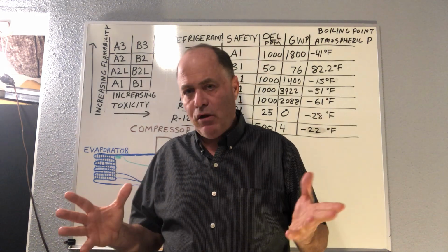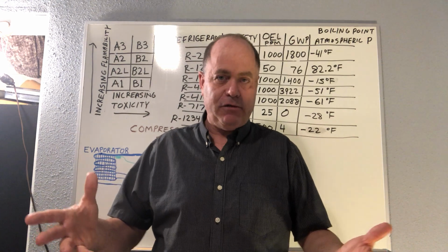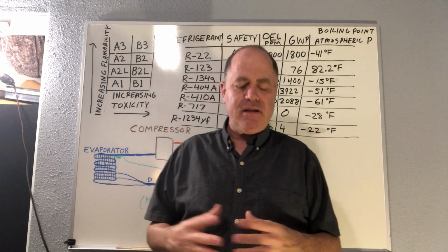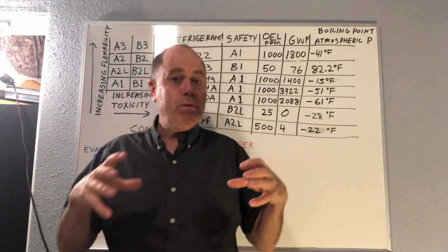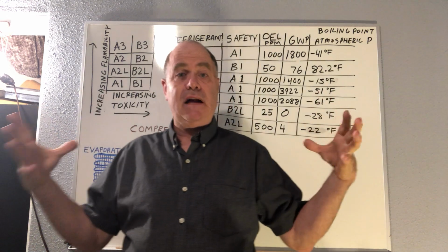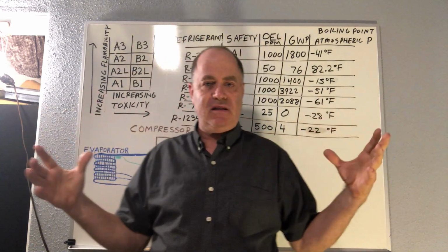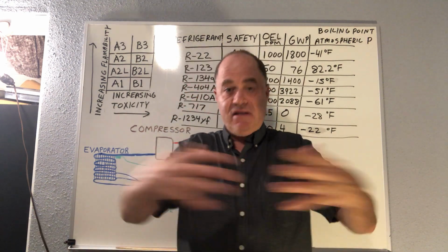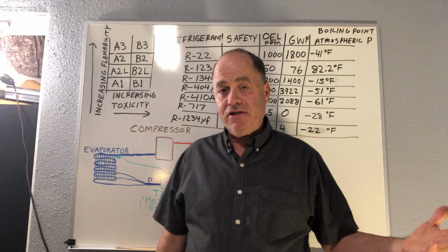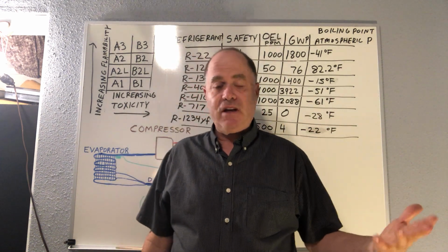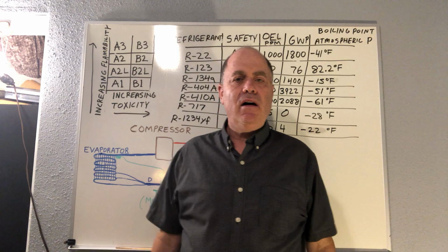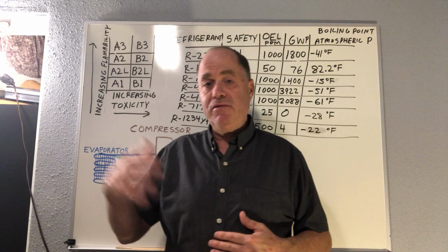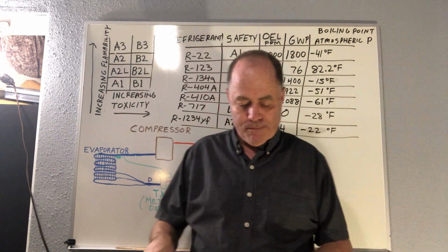So even though they're kind of high probability systems that you could get some refrigerant in there, that's okay according to the code. Then low probability systems are where we actually put our big equipment that holds a lot of refrigerant, because those aren't in occupiable spaces. If something holds a tremendous amount of refrigerant, you don't want it to be where people are, because a giant leak could cause an environmental situation, cause people to suffocate and like that. So that concept of high probability and low probability, and we have different regulations for chiller rooms than we do for your bedroom at home, okay?